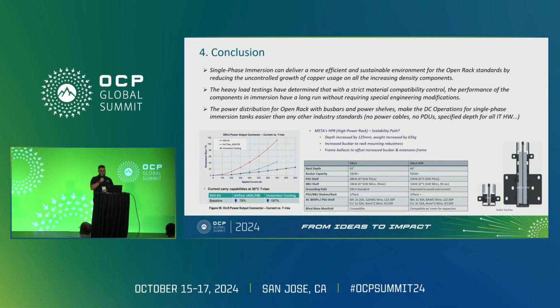To jump to the conclusion, we believe single-phase immersion cooling can deliver a more efficient and sustainable environment for Open Rack standards. We've been doing it for Open Rack version 2, we're doing it now for version 3, and we hope for version 4 if it comes at some point. The good thing is that all these load tests prove the conceptual idea — having this in immersion and gaining more efficiency — is actually happening.